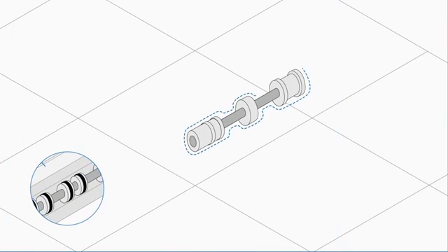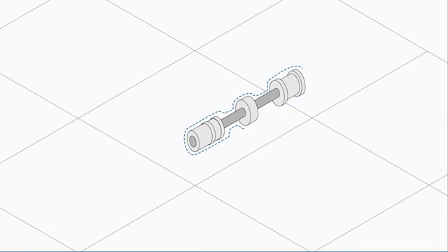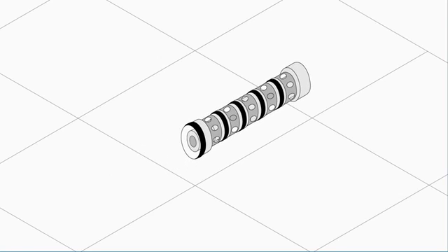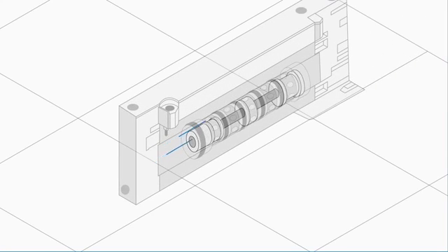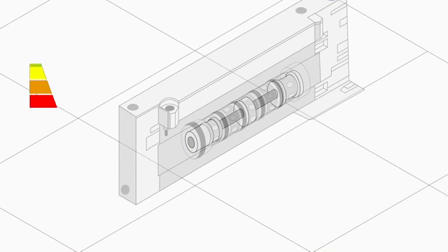A metal seal valve doesn't have rubber seals, but is manufactured with extreme precision, and its piston glides on an air bearing. This allows it to change modes without friction, making it practically immune to wear. It's also less sensitive to air quality, and resists vibrations because it's mechanically held in place at both ends. It may therefore be used in safety circuits.